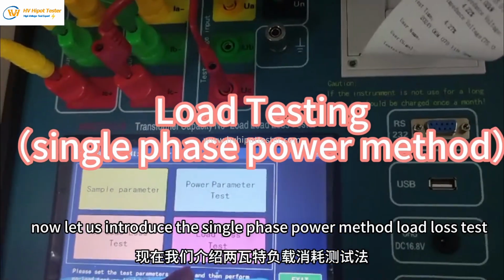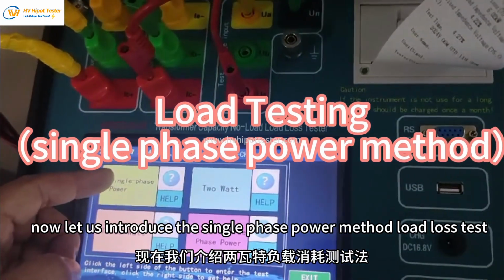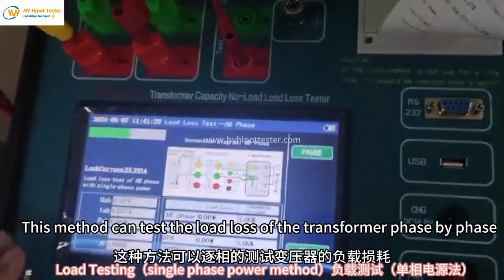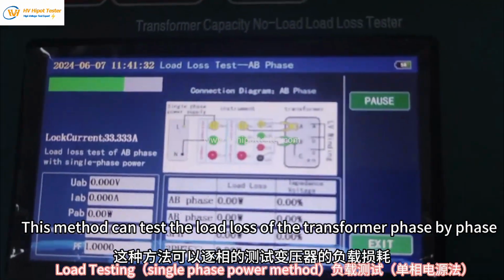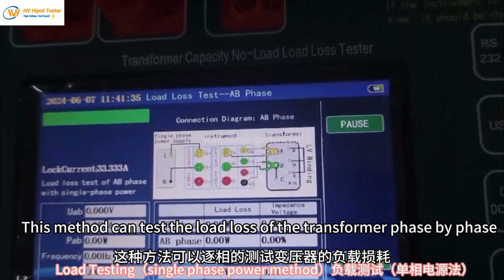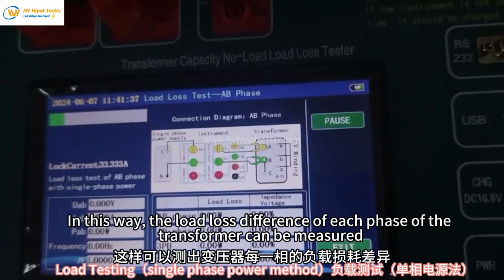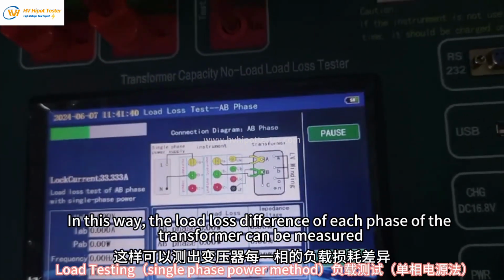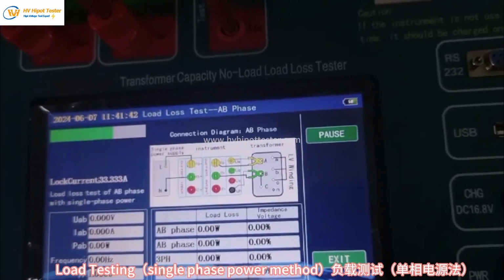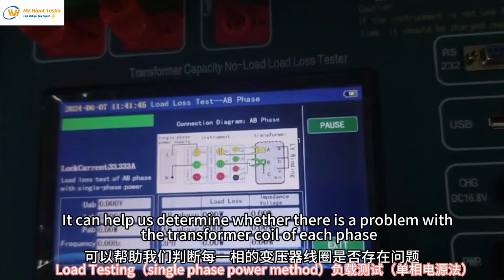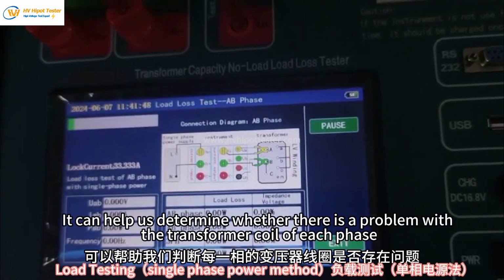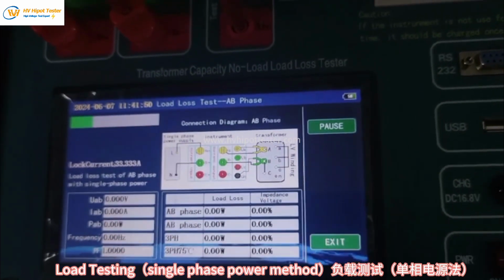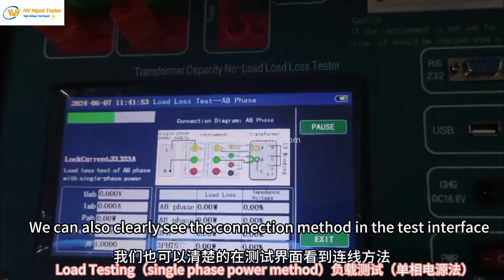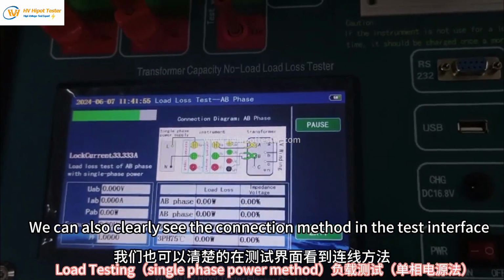Now let us introduce the single-phase power method load loss test. This method can test the load loss of the transformer phase by phase. In this way, the load loss difference of each phase of the transformer can be measured. It can help us determine whether there is a problem with the transformer coil of each phase. We can also clearly see the connection method in the test interface.